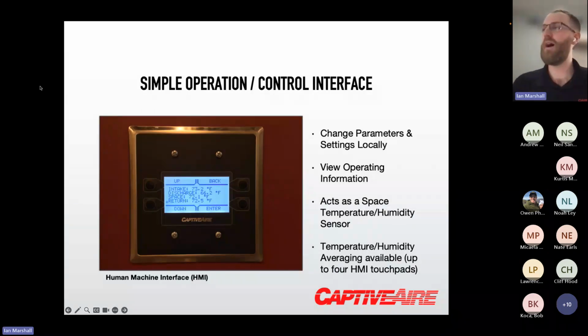So this is called our HMI, or human machine interface. One of these is factory mounted. It's an LCD screen with 4 touch buttons. One of these is factory mounted in the controls cabinet, standard on every unit. And then one will ship loose and can act as a space temperature and humidity sensor if you'd like, or it could just be installed in a manager's office to act as an interface with the unit without having to go up to the roof. We also can daisy chain up to 4 of these to act as space averaging sensors as well. So convenient to have in the space.